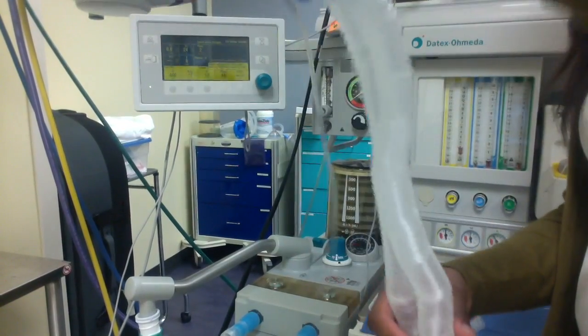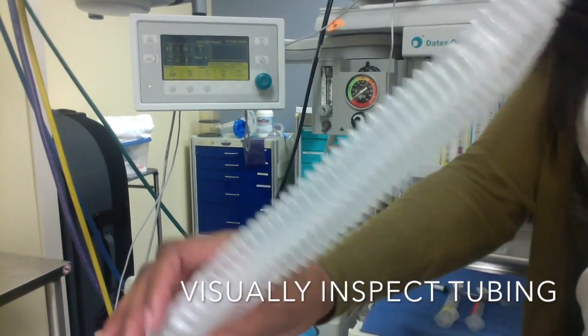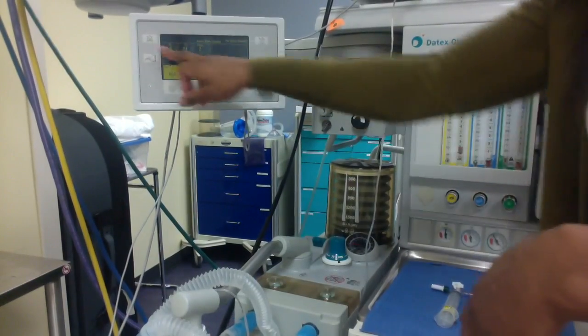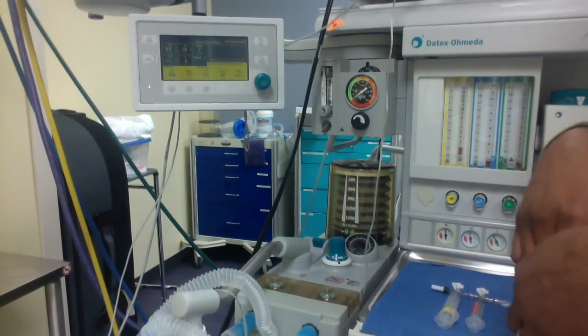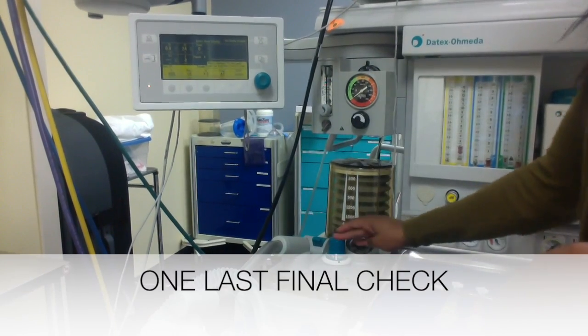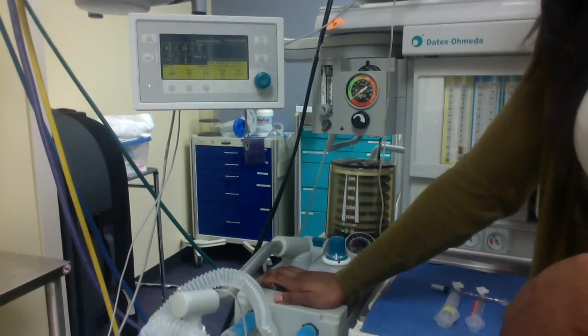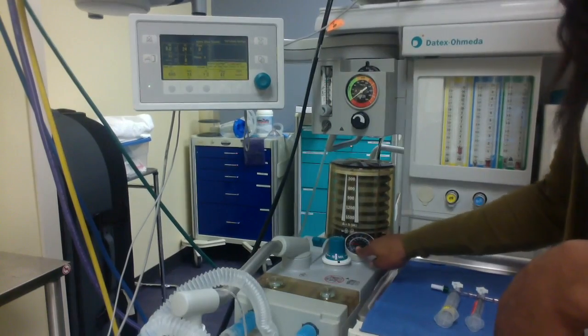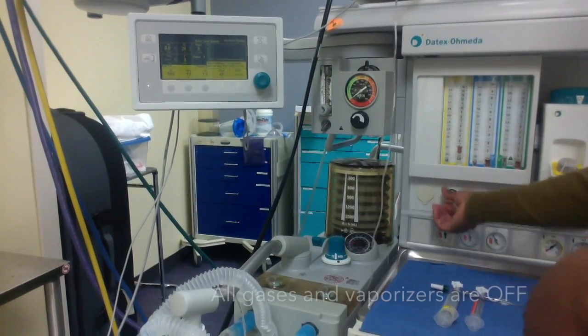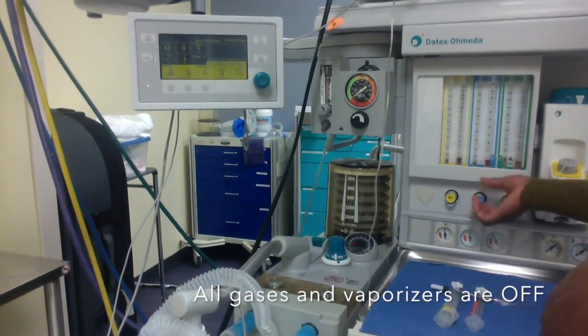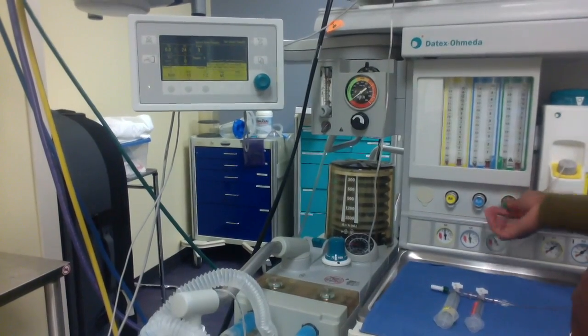I'll also take one quick look at my circuit and make sure there's no cracks in the tubing, and I put that back. Then I flip this into standby. I make sure that my APL valve is open. My unidirectional valves are flat and seated. My circuit is reading 0 centimeters of water. I have no flows going, so no air or oxygen or nitrous being delivered. And that my vaporizers are off as well.